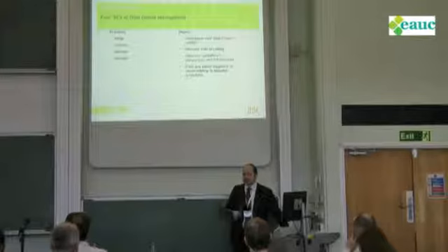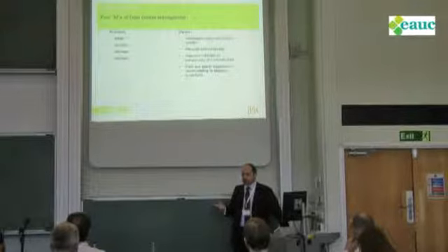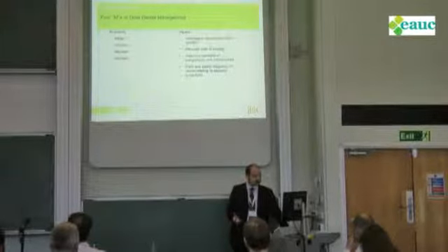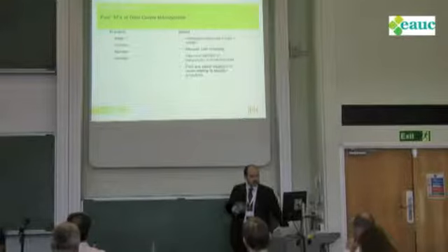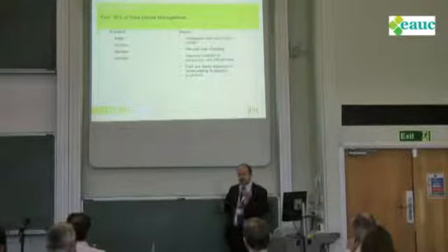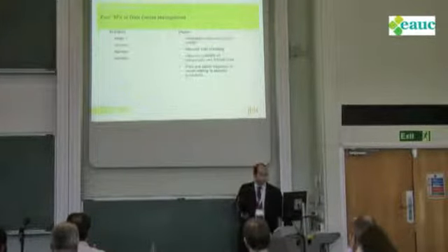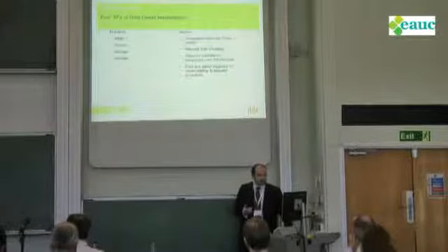Sub-meter it, because you've got to understand the size of the problem that you have. It also gives you a profile for your data center, how it operates, and what it costs you. So you're monitoring your profile, and if you see any changes, you can identify where those changes are, what's causing them, and then tackle them.